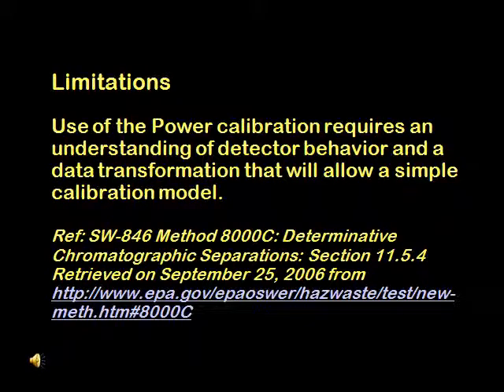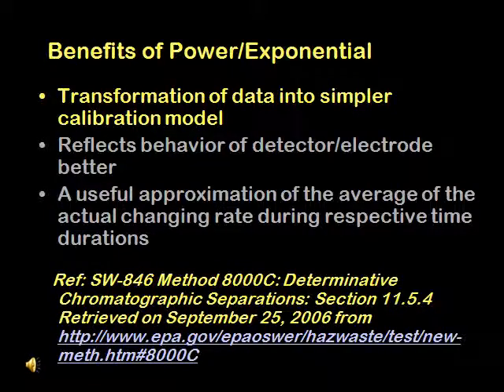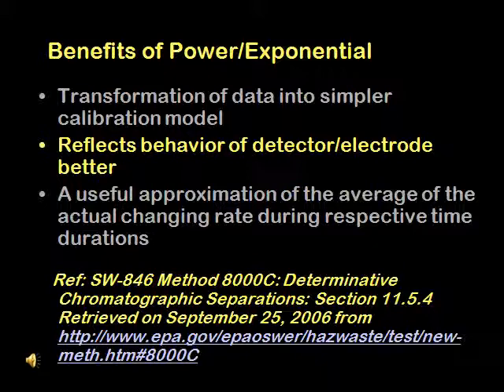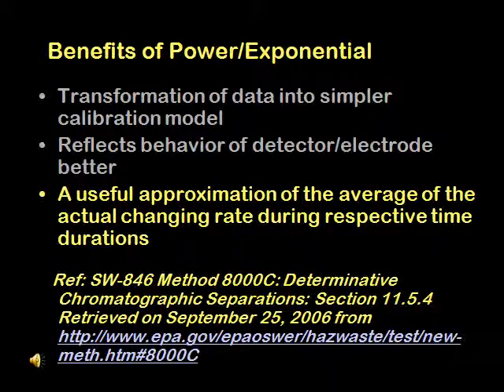Use of the power calibration requires an understanding of detector behavior and a data transformation that will allow a simple calibration model. The benefits of using a power or exponential calibration is that the transformation of data into a simpler calibration model makes solving the calibration easier. It can reflect the behavior of the detector or electrode better, and the calibration models provide a useful approximation of the average of the actual changing rate during respective time durations.